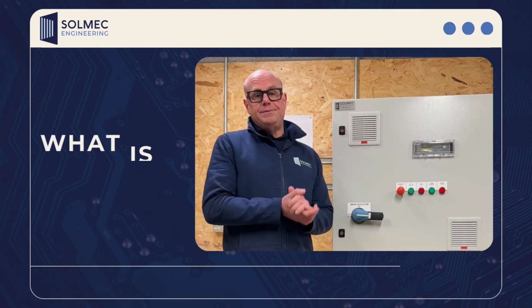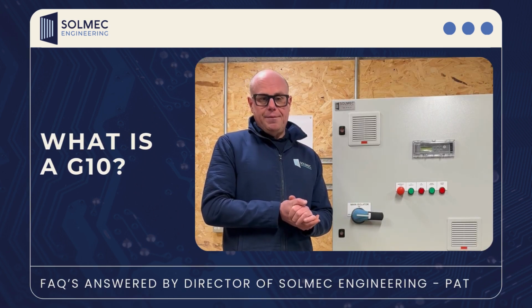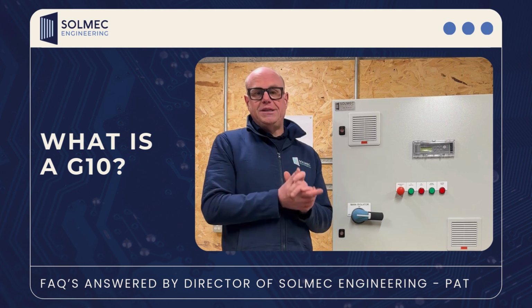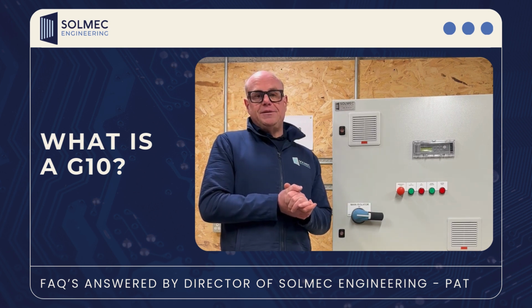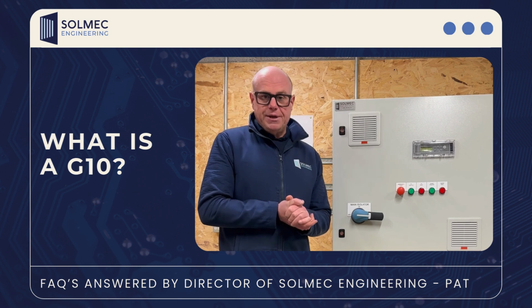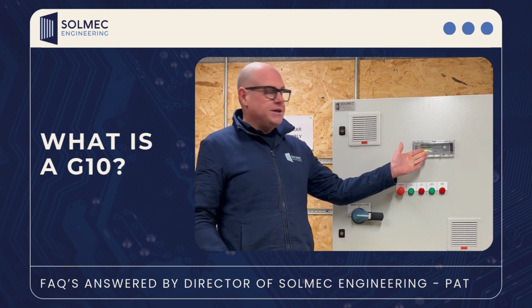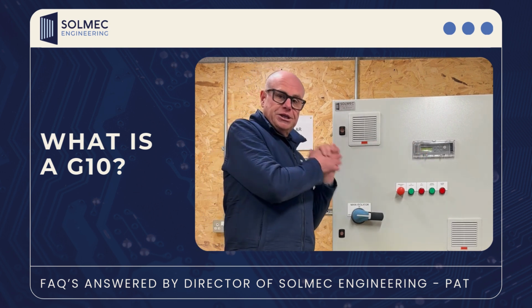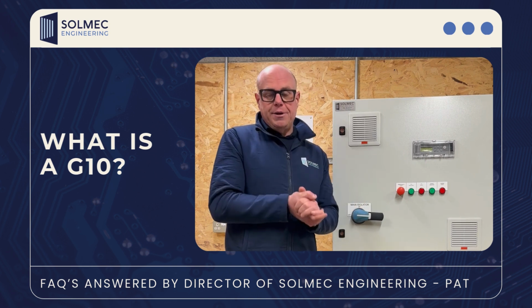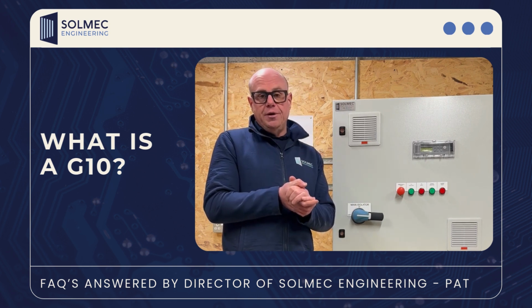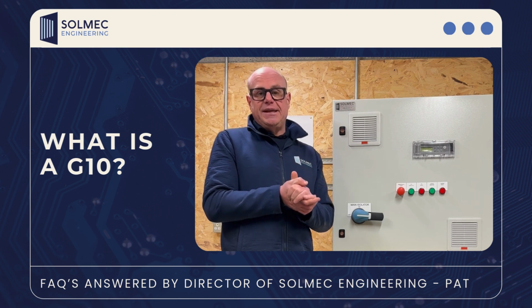So what is a G10? A G10 is a relay. You've probably all heard the phrase EGIP. What EGIP stands for is Embedded Generation Interface Protection, and that's all the G10 is. It's an interface protection between the generator and the grid. It protects both of them really from each other in very specific settings that the ESB have set out.